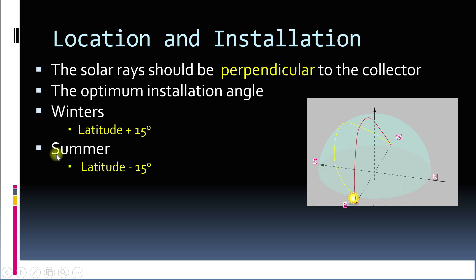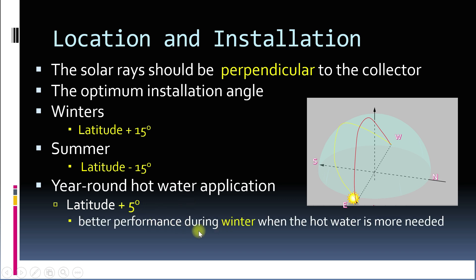If you need hot water in summer, the angle should be latitude minus 15 degrees. For year-round use, which may be a requirement for industries or hotels that need hot water all year, the angle should be latitude plus 5 degrees. This angle ensures better performance in winter when hot water demand is usually higher.